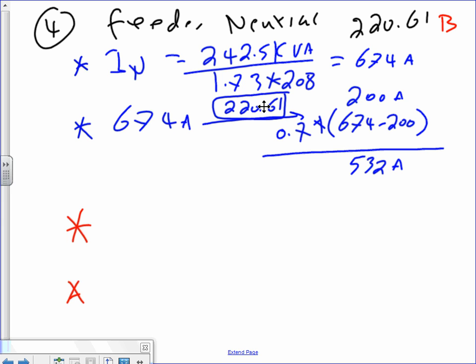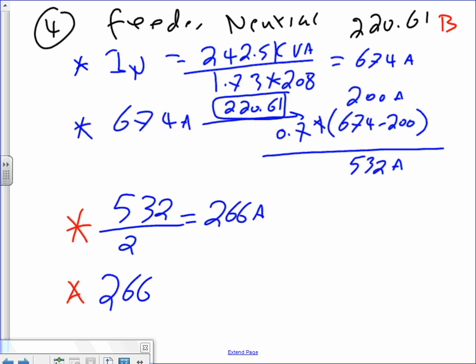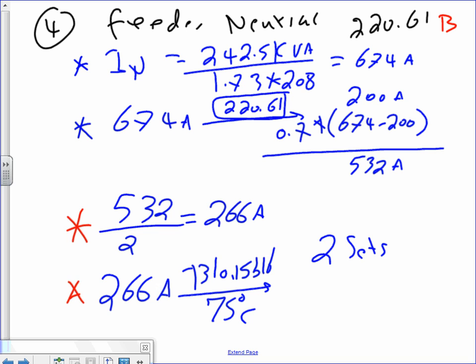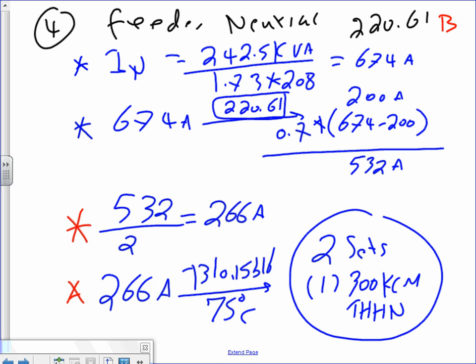Okay, now we need to parallel. You take the 532 divided by 2, because we're already paralleling 2. That will give you 266 amps. You take the 266 amps, same table, table 310.15 B16, 75 degree column. That will get you two sets of one conductor, 300 kcm THHN.